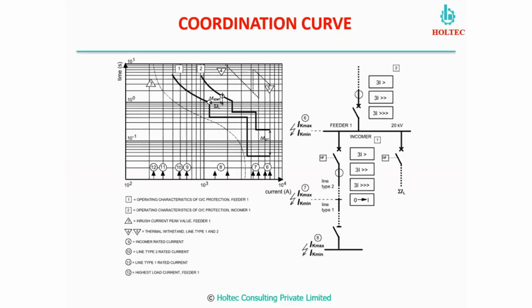The fault may be of dead short circuit nature or dead ground nature, or it can be a partial short circuit or partial ground. So the amount of fault current flowing in different fault conditions will vary very widely. Any calculation through Excel will not give sufficiently proper coordination of the system. Then what next? What solution do we have? The solution is the settings through software, where we can have selectivity curves. These coordination curves or selectivity curves we can obtain from the software.